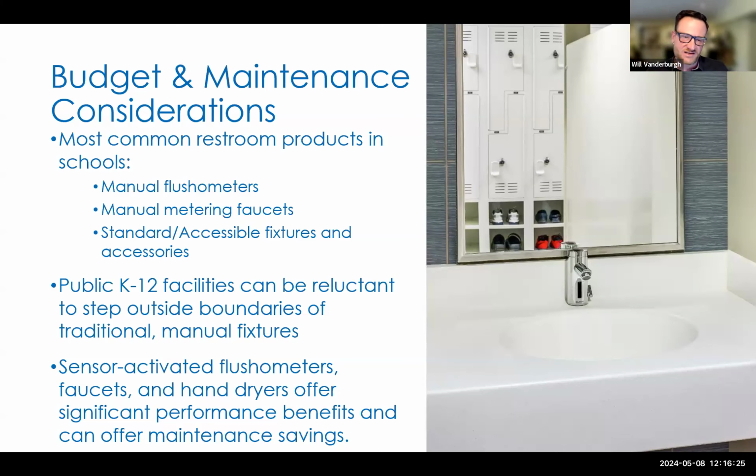So the sensor activated flush valves take away that kicking opportunity for the user. So we find they tend to flush more predictably, more regularly. As well, there's options that can be set up so that they flush that bowl on a regular basis so that the waste is kept clear, or the fixture is kept clear. Traps and urinals, for instance, are kept filled, particularly during the summertime months. And then faucets as well.